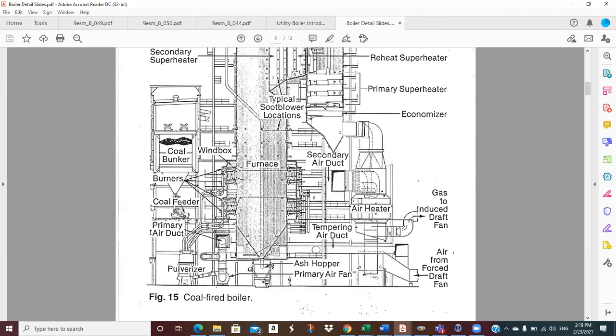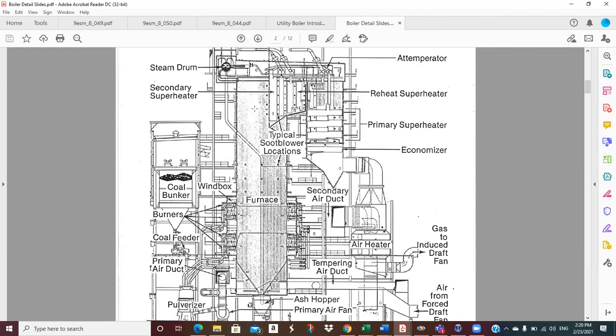We're showing soot blower locations because in a coal boiler, you'll form soot, slag, ash will stick, and periodically you have to blow that stuff off. If it slags up, you can't transfer heat. That slag is like an insulating layer, and you have to blow that stuff off. So you've got them in there in your furnace. With those are IR blowers, and they call the ones in the convection pass, I think, IK blowers. And some of them are wall blowers. Some of them just blow a section of wall. Others extend way out in the furnace. So there's some different technologies. All this stuff is pretty complicated, but there's different technologies on soot blowers.